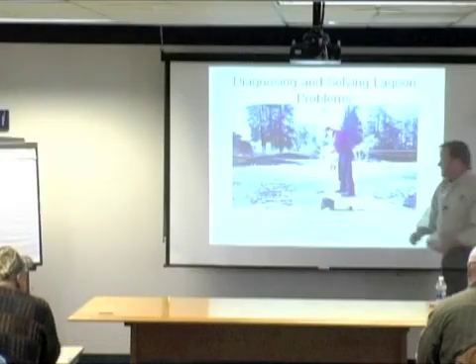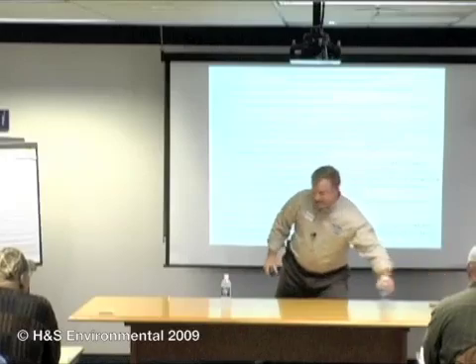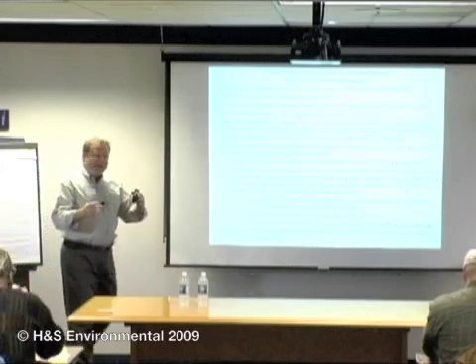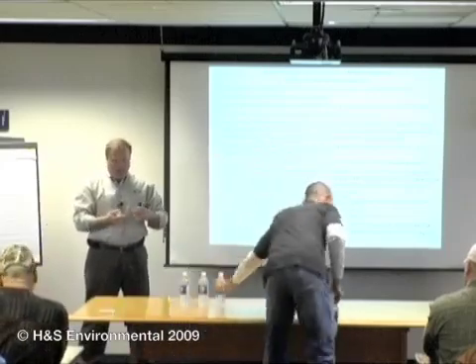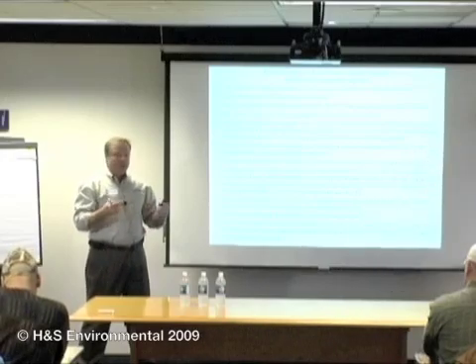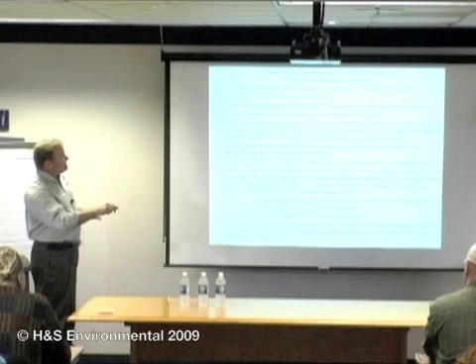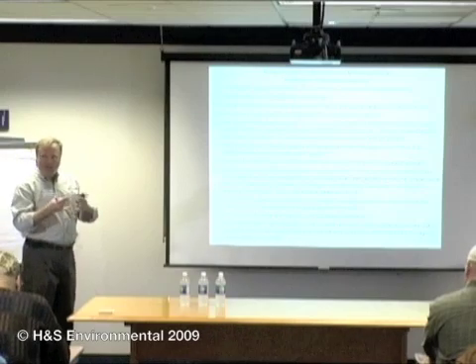Let's talk about diagnostics. There are about 11 things you need to know to effectively solve problems in lagoons. The first is to look at whether the system is properly sized for the community, industry, or load. Can your pond handle the load? You need to know the pond dimensions and depths, the theoretical and actual retention time, and the flow — even if you don't have a flow meter and have to calculate from pump run times.